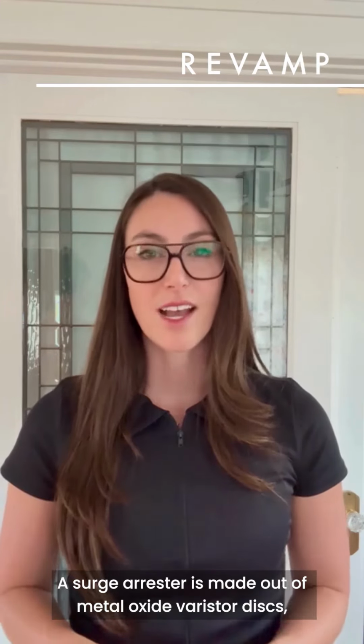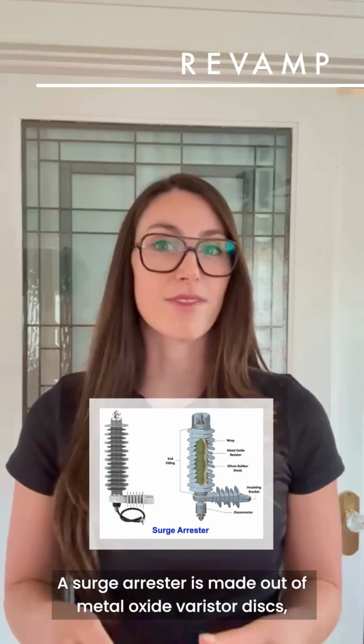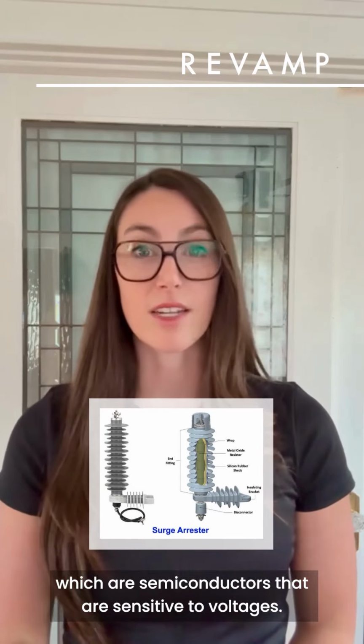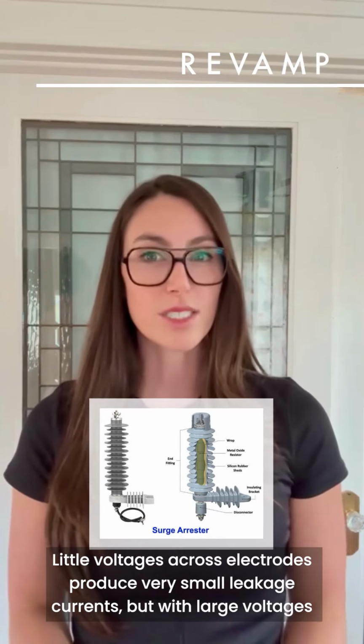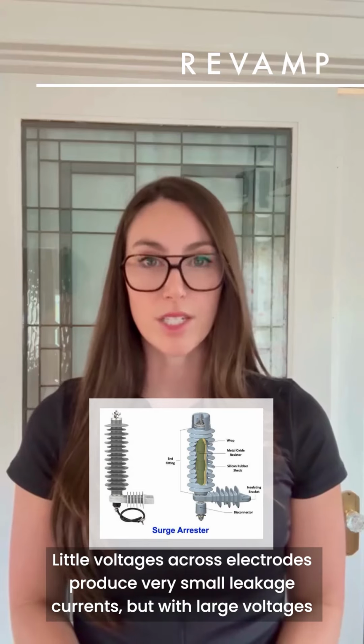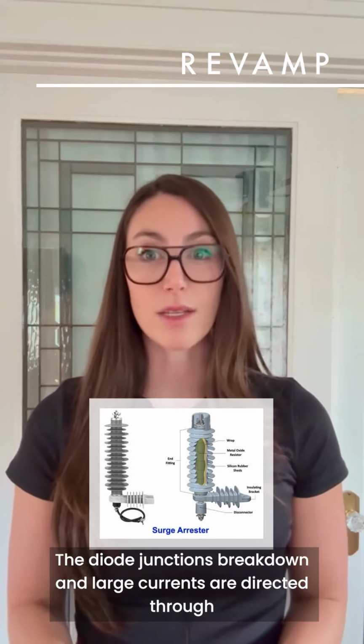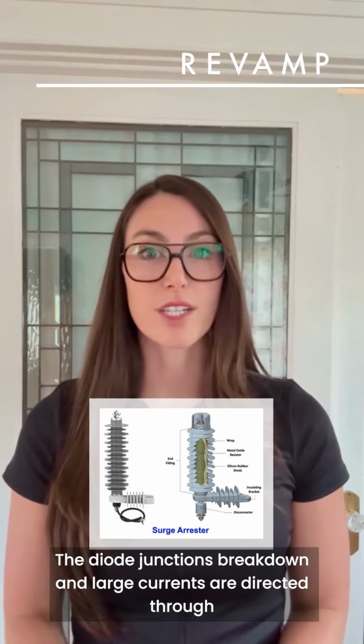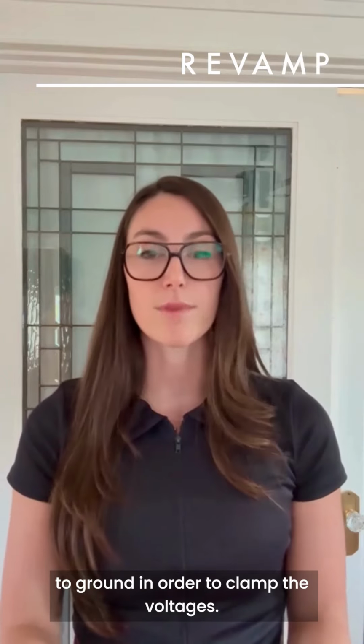overvoltage surges. A surge arrestor is made out of metal oxide varistor discs, which are semiconductors that are sensitive to voltages. Little voltages across electrodes produce very small leakage currents, but with large voltages, the diode junctions break down and large currents are directed through to ground in order to clamp the voltages.